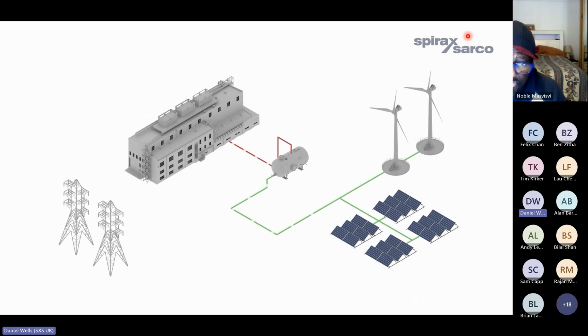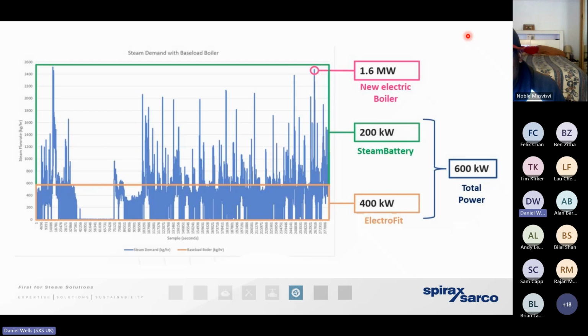So, for example, we have a client down south that needs steam to exist at exactly 121 degrees to satisfy the requirements of a number of autoclaves. At 121 degrees, the pressure-temperature relationship tells us that we need to produce steam at 1 bar gauge. So if we're reducing the pressure of the steam from 30 bar gauge to 1 bar gauge, we know the mass of water that's going to boil off and produce steam. So it all really comes down to the mass of steam that the client requires to help us understand the size or capacity of the steam battery that we need to engineer.